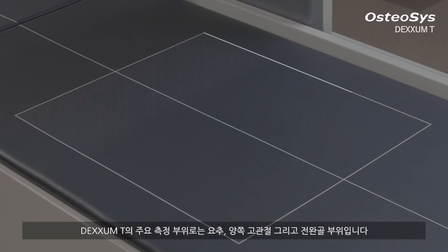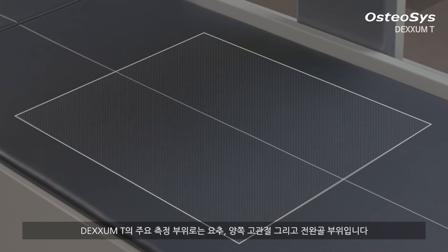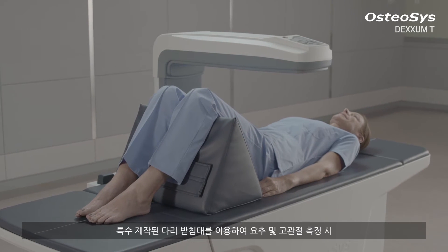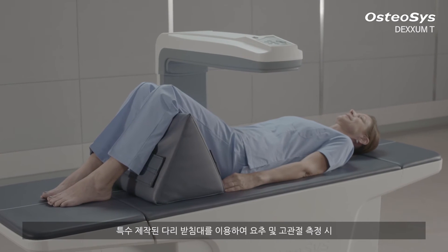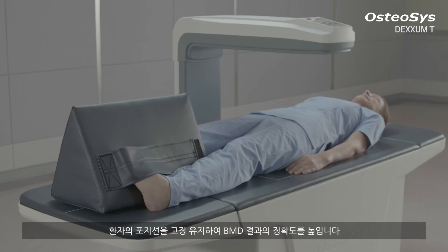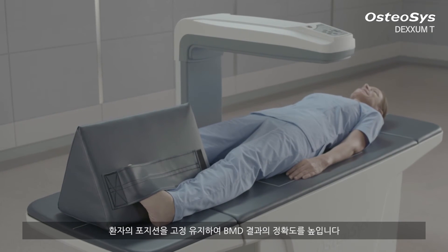The major scan areas for DEXXUM T are AP spine, dual femur, and forearm. When you measure the BMD of lumbar spine and femoral neck, a specially designed foot supporter helps the patient to have a fixed position, which naturally increases the precision of your BMD results.